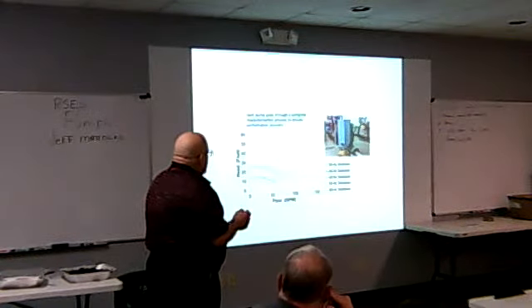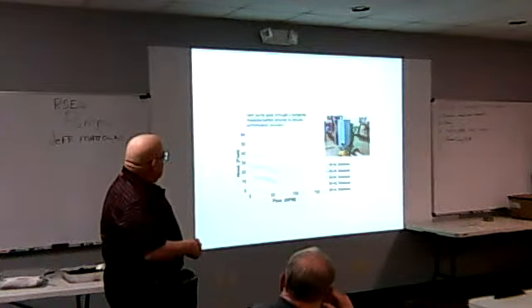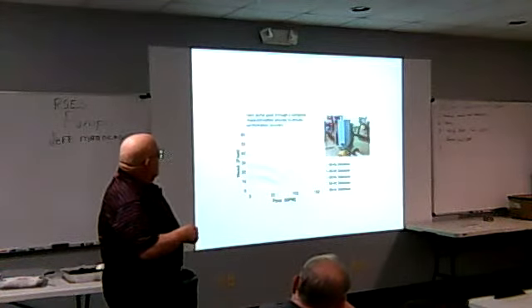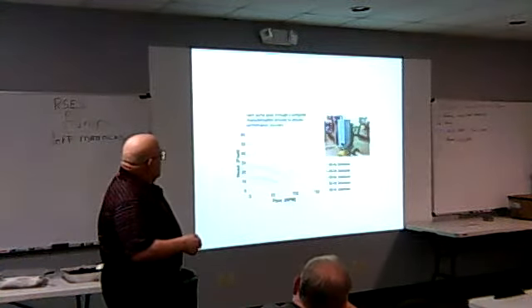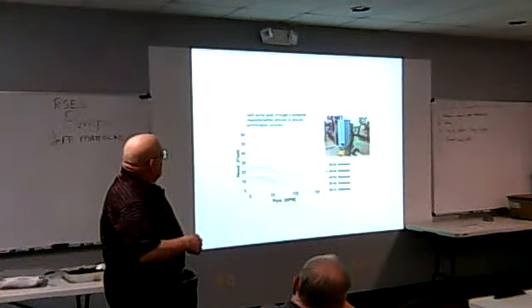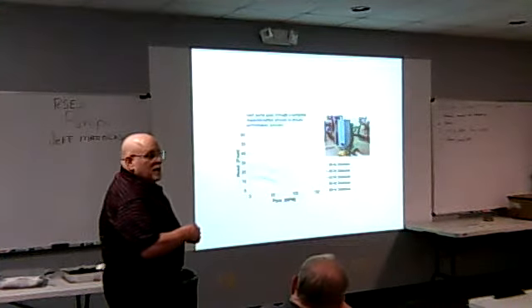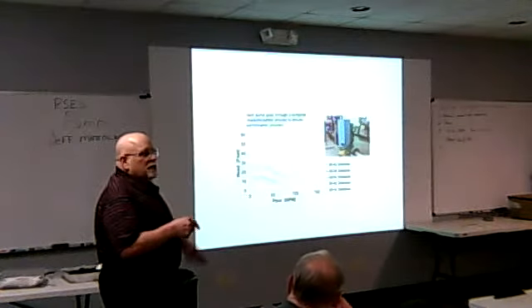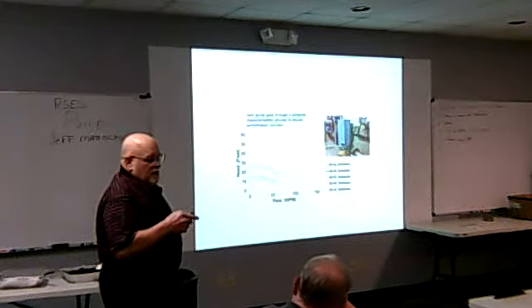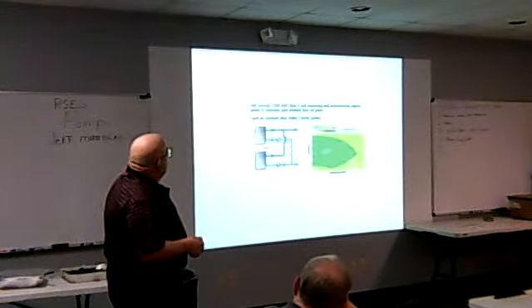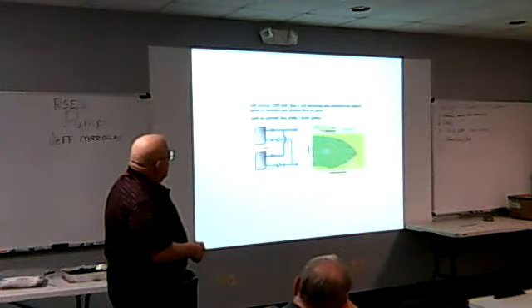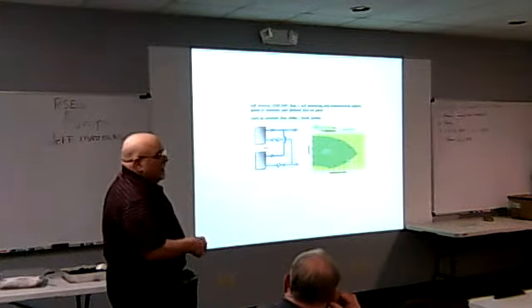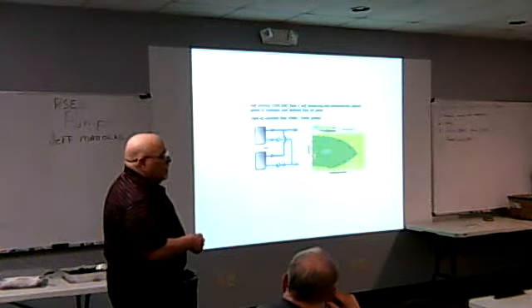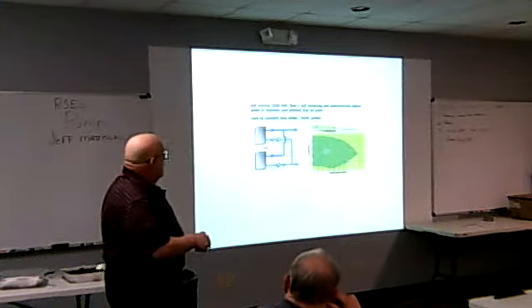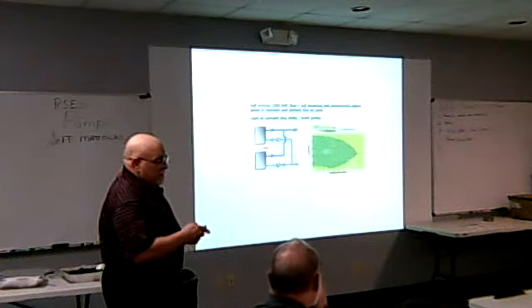And what they do at the factory, they take a specific pump and they actually plot every impeller diameter in the computer on this pump. So it knows specifically at 100 GPM, I'm at 35 feet of head, at 50 I'm here, and so on and so forth. All that data is put in the computer. It's all in that drive. When you see a self-balancing curve, this is your performance area. You no longer look at impellers. As long as I'm in this window, my pump will handle whatever set point is in here. Okay?